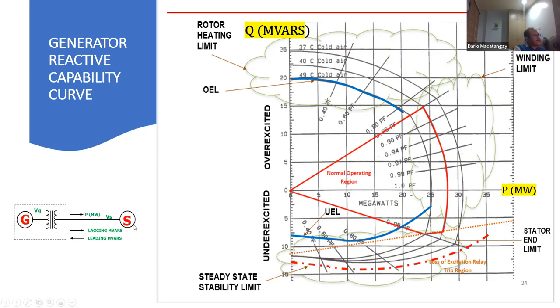You also need to support the megavar requirement of the system, because the system itself has loads, like your cities and your industrial plants, everything connected in the transmission system. You need to run the motors, and the motors require megavars to run. Therefore the generator needs to supply the megavars, and that's provided from the excitation system. Now, there are two types of megavars. They could be lagging or leading. Those are two things that need to be considered when you're trying to implement a protection system for generators.